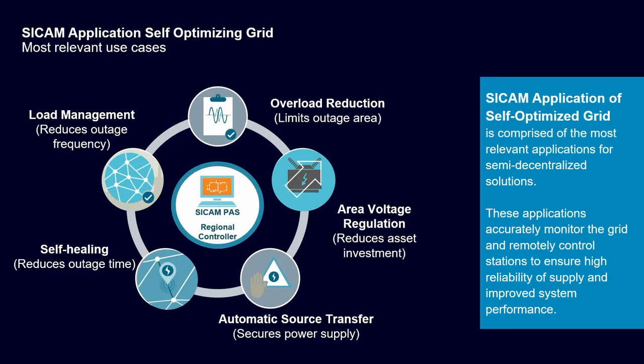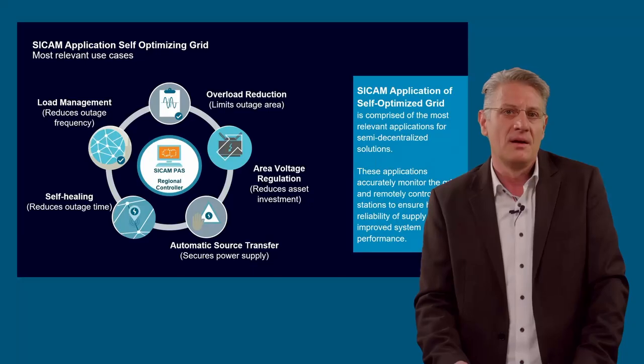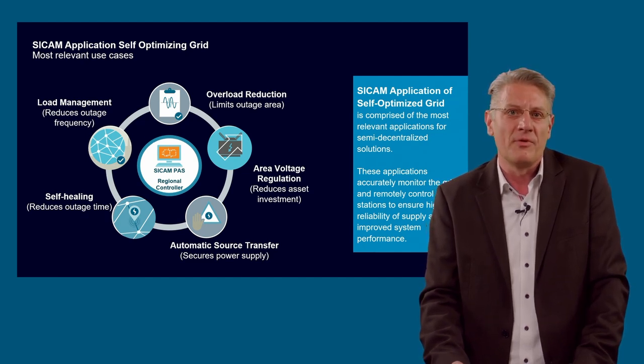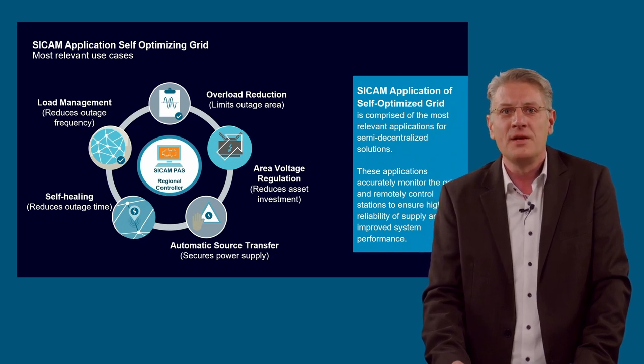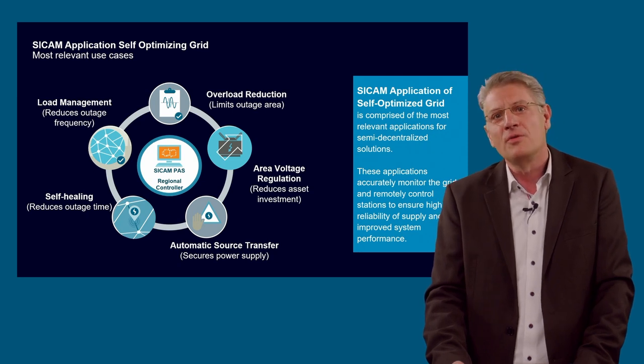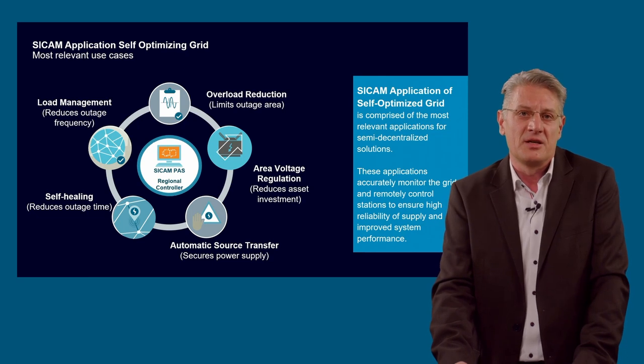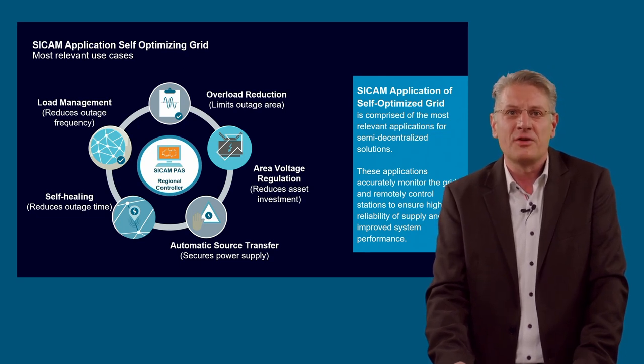The SICAM self-healing mechanism: the SICAM application of self-optimizing grid is comprised of the most relevant applications for a semi-decentralized solutions. These applications continuously monitor the grid and remotely control stations to ensure high reliability of supply and improved system performance in a closed-loop implementation. For self-healing, we integrate functionality for self-healing and automatic source transfer. For balancing load and demand, there is load management and overload reduction. And for fluctuating loads created by electric vehicles, there is an area voltage control functionality.